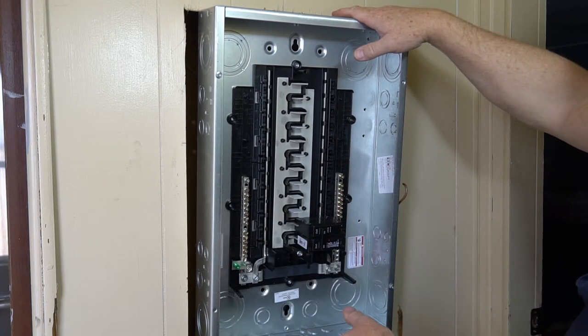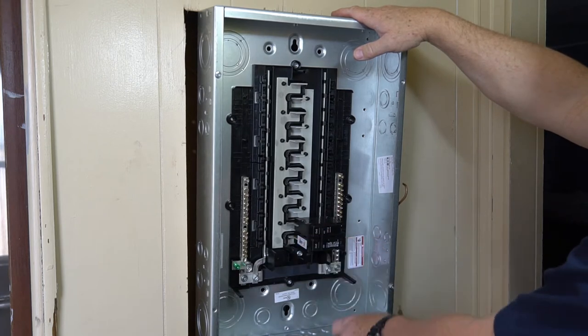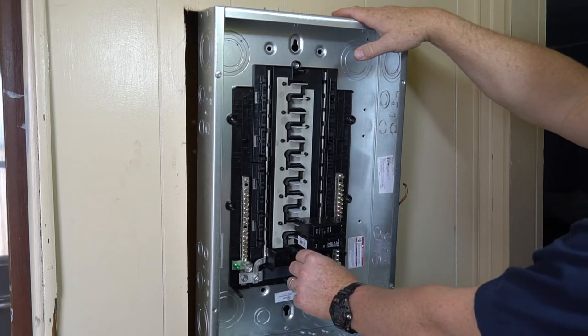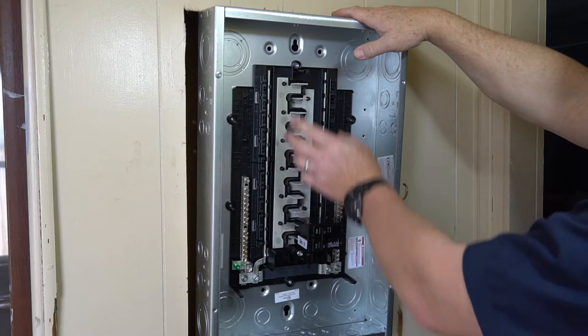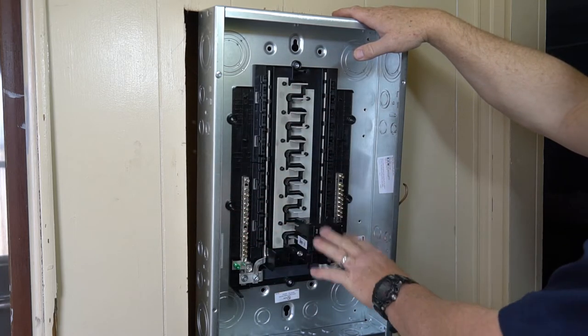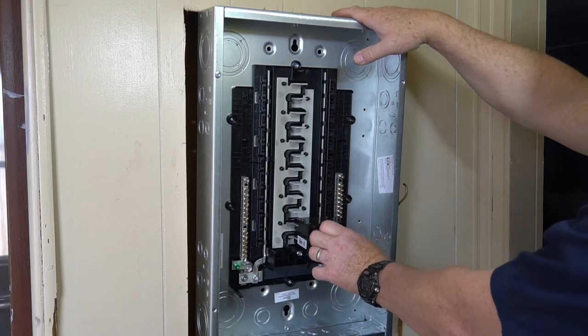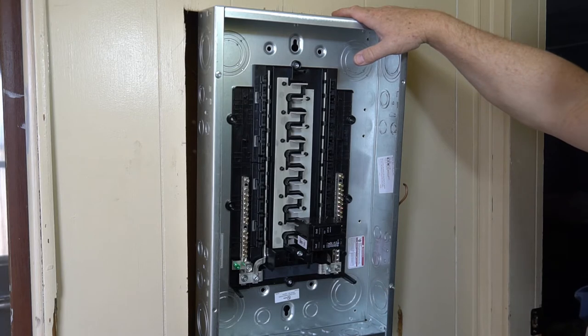In the worst case scenario that I needed to turn it upside down, the main breaker is movable — it does have a little keeper tab that holds it on, but it can be moved to the other side of the box. This is not the case on all breaker panels; some are a permanent installation. In this case it's just a big 100 amp double-pole breaker, so it is movable.